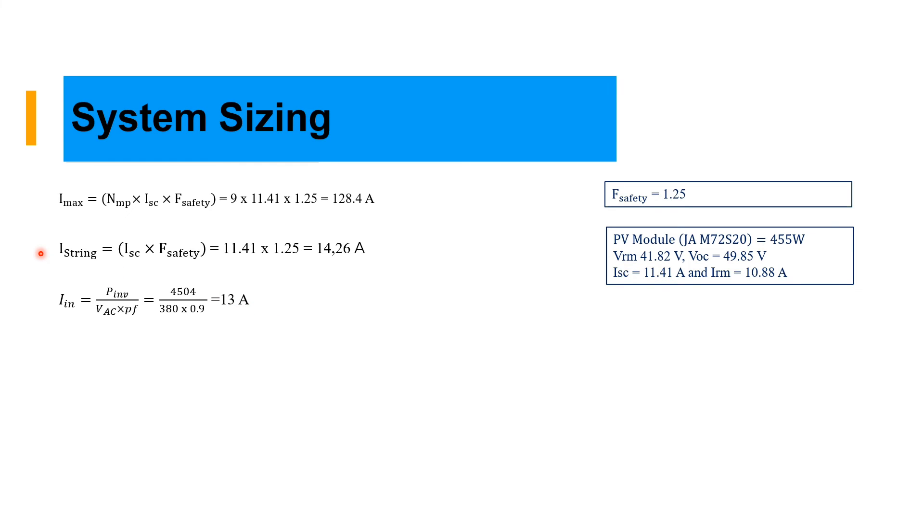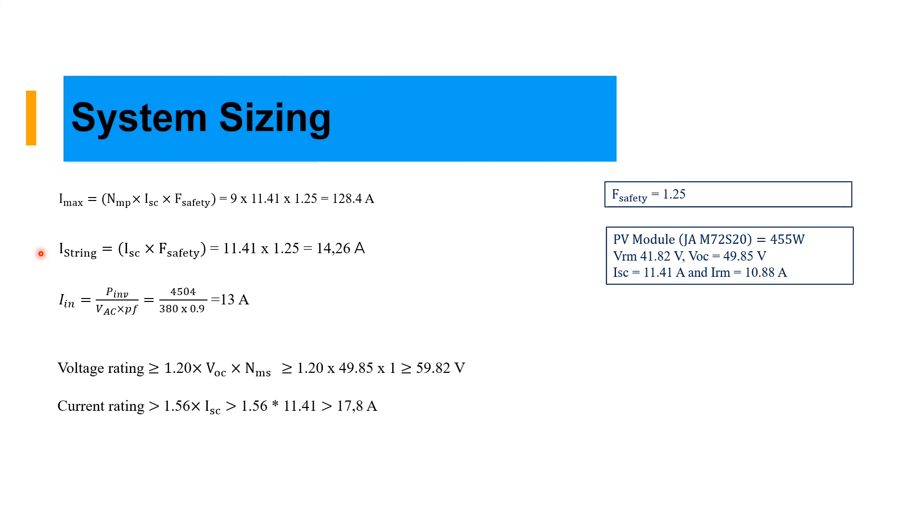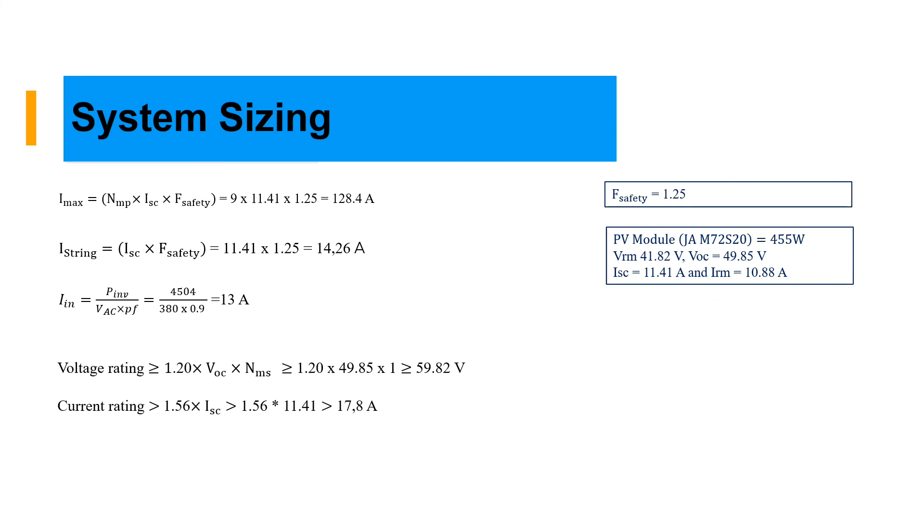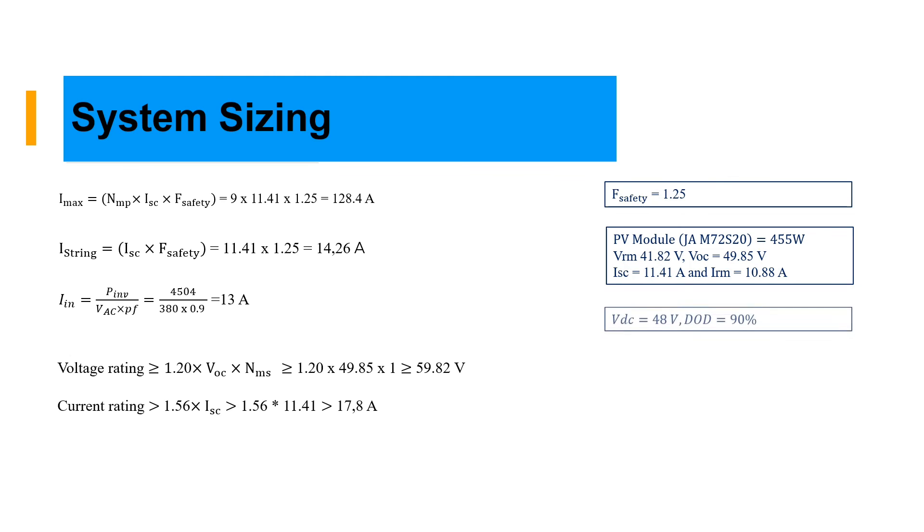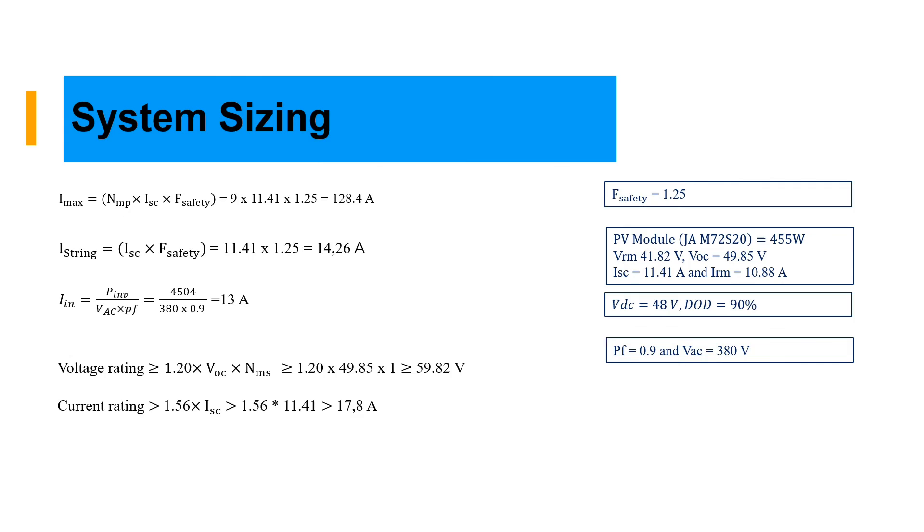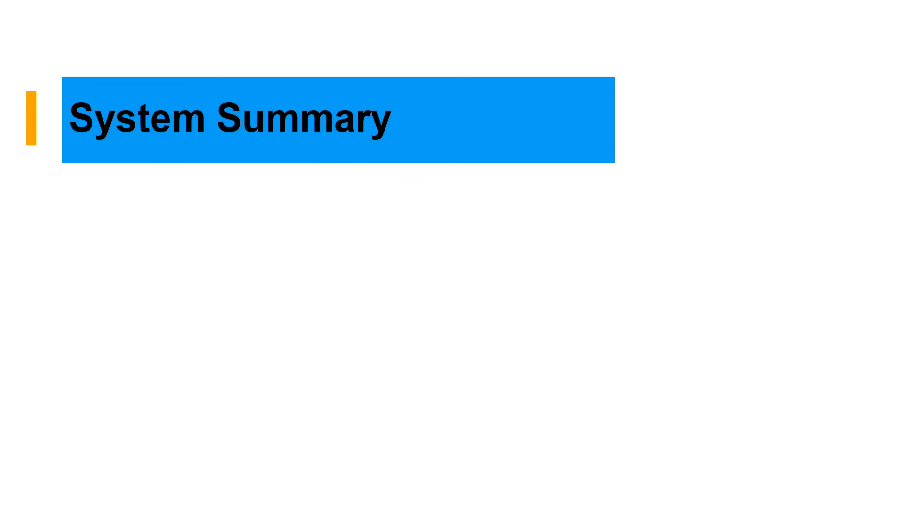Then we have our inverter power divided by the three-phase system times power factor. We have our voltage rating for the size of the protective device. Voltage rating and current rating should be equal or greater than the value of 59.82 volt and 17.8 ampere. When choosing your protective device, you should always consider this voltage and current. As you can see, power factor and the AC voltage.